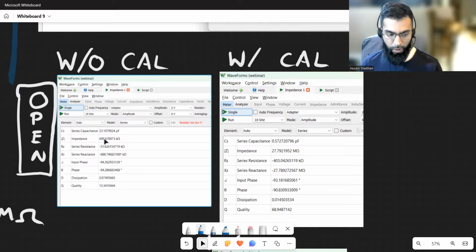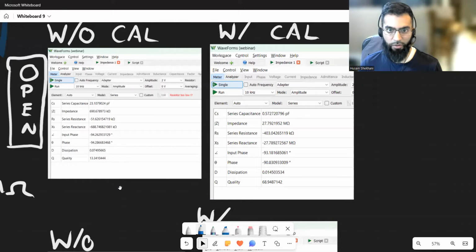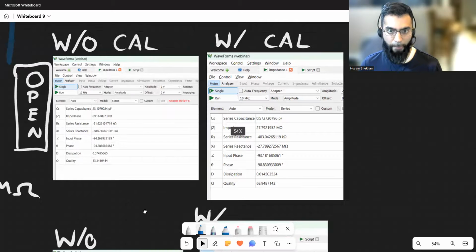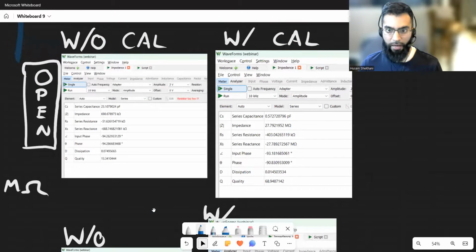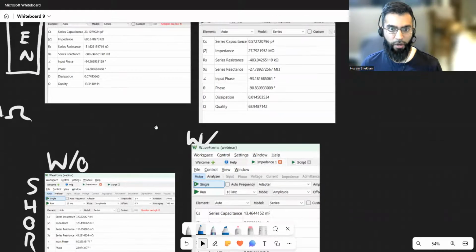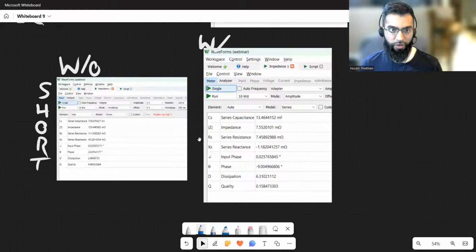I'll mention that devices that have a very high anti-resonance impedance, high coupling factor devices, those definitely you'll need to do open circuit calibration. But especially higher frequency devices; for lower frequency devices like 40 kilohertz, sometimes you may not need to do this step. But nonetheless, you don't lose anything by doing it. So go ahead. It really affects the anti-resonance impedance and its frequency if you do not compensate, but that depends on your transducer.